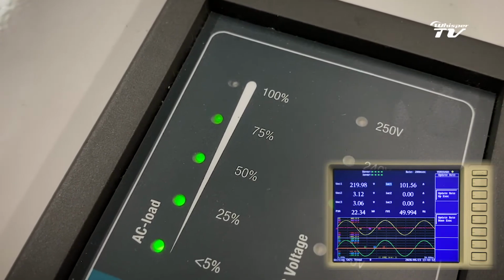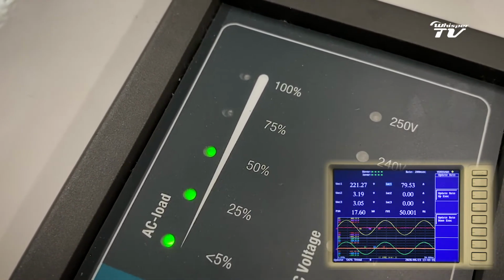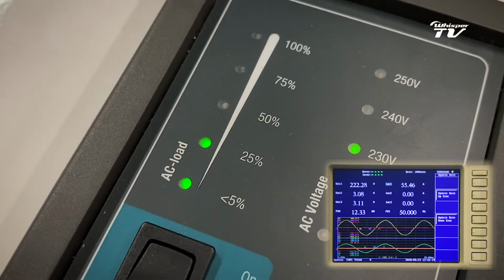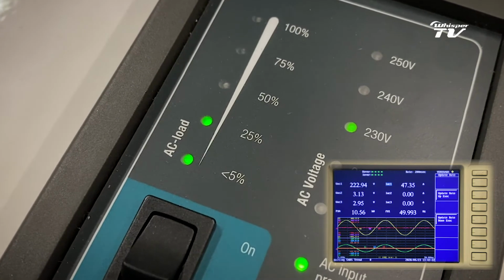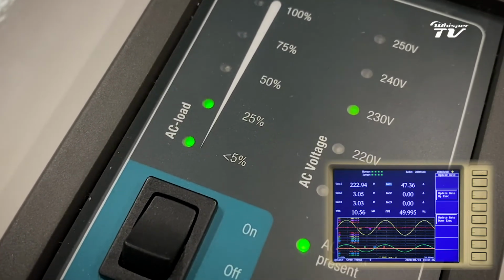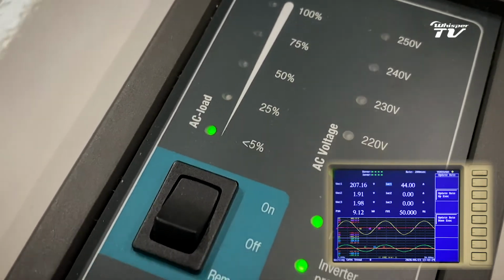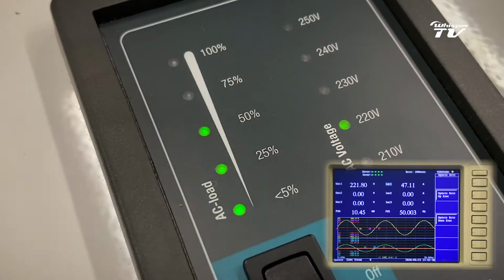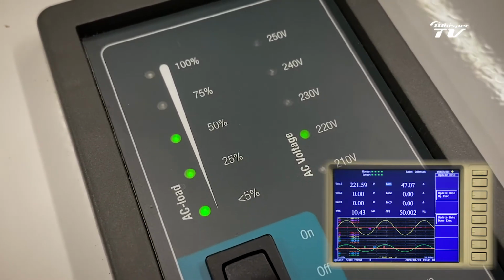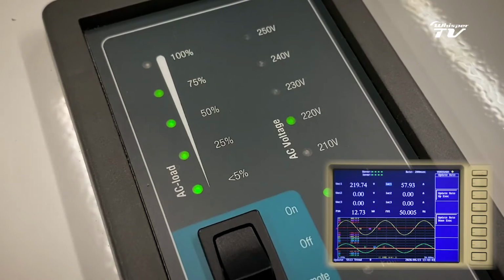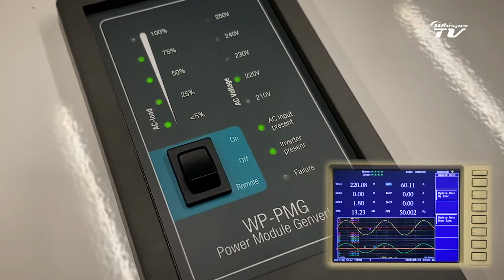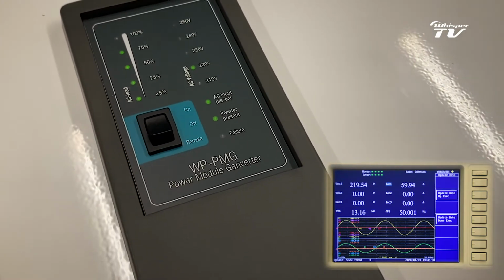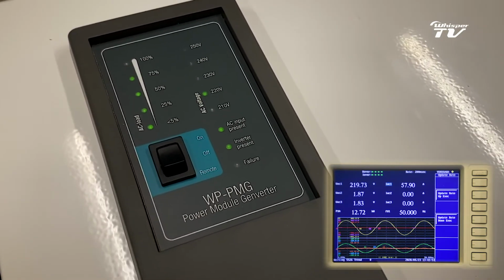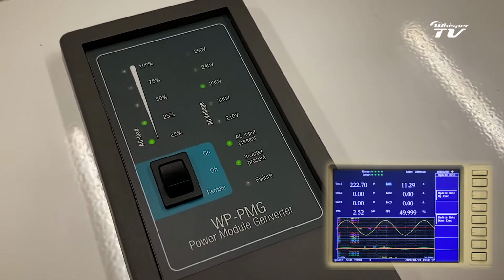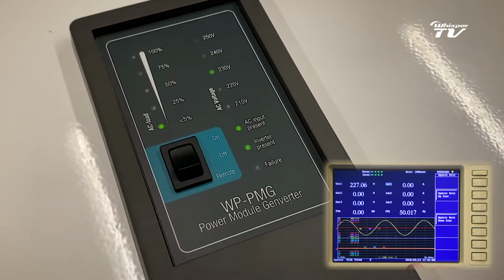What we are going to do now is switch off some loads, as we do not need that much anymore. We are about 10.5 kilowatt, and we stop the first generator, so that's going to stop right now. You can see that the second generator is doing the load, about 10.5 kilowatt. I can put a little bit more load on it. I now have 12.5 kilowatts roughly, a little bit more, 13 kilowatt. Everything is done, so we are now going to switch off the loads, and we are stopping the second generator as well.